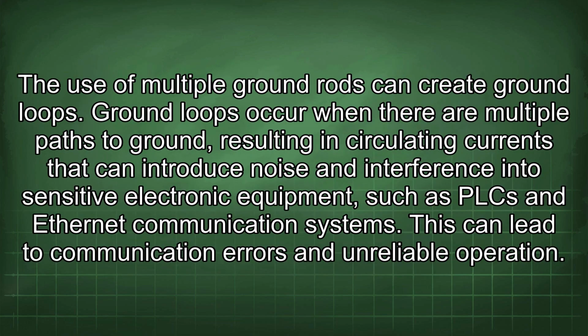The use of multiple ground rods can create ground loops. Ground loops occur when there are multiple paths to ground, resulting in circulating currents that can introduce noise and interference into sensitive electronic equipment, such as PLC and Ethernet communication systems. This can lead to communication errors and unreliable operation.